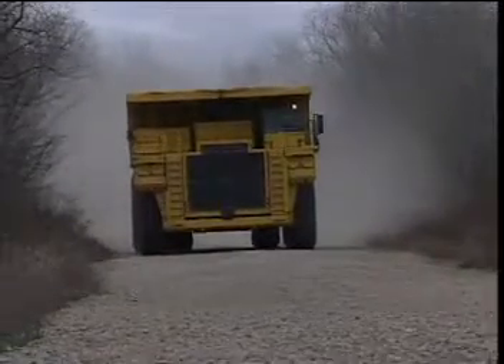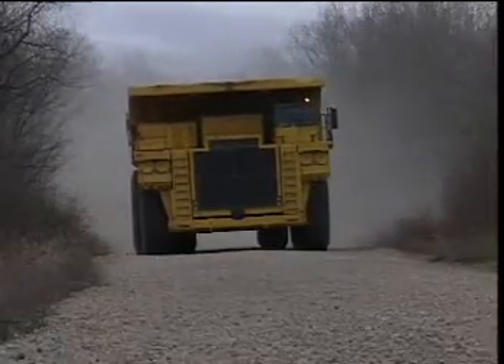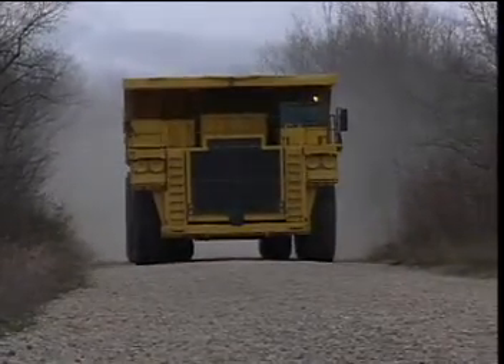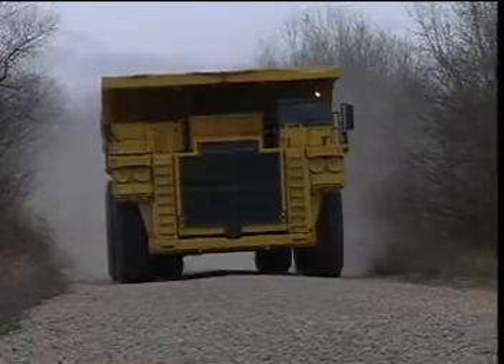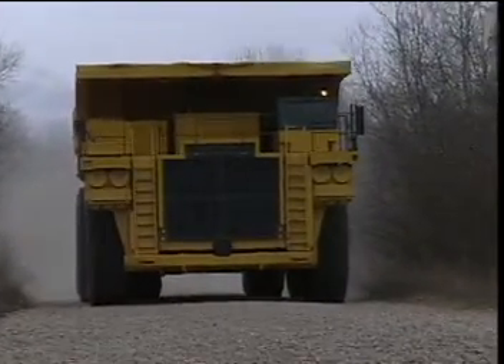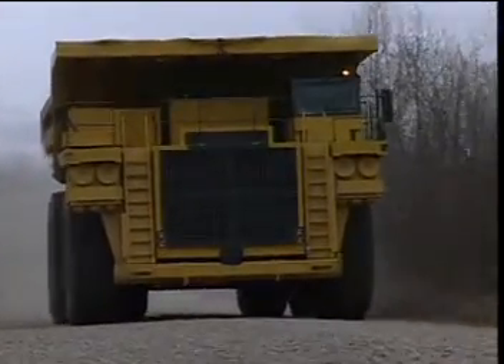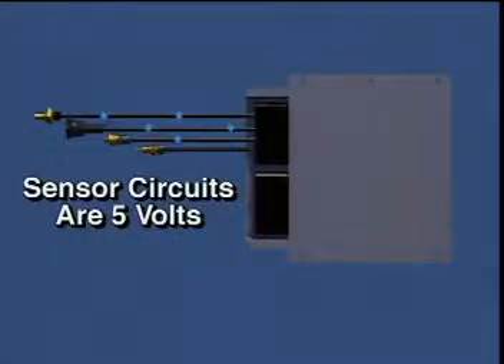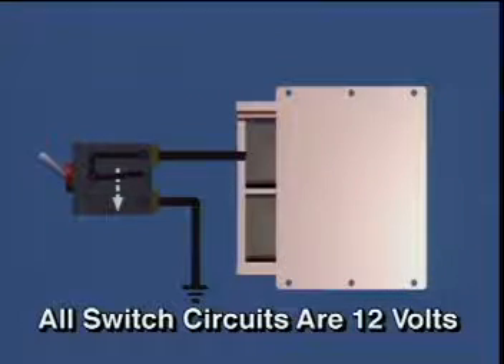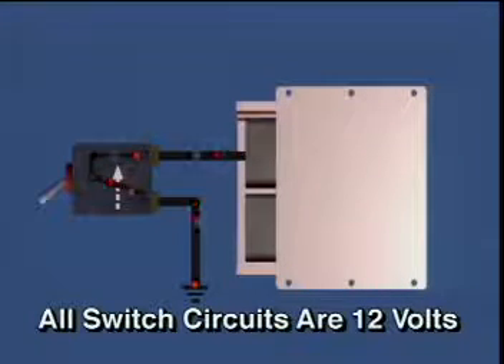The QSK 45 and 60 Quantum engine control system is a 24-volt system. In order to properly troubleshoot the control system, it is necessary to understand the various supply and operating voltages. The sensors within the system operate on a 5-volt supply signal. All of the switch circuits within the system are 12-volt circuits. Closing any of these switches causes the voltage in the circuit to be pulled to ground, indicating to the ECM that the switch has been closed and the appropriate action is requested.